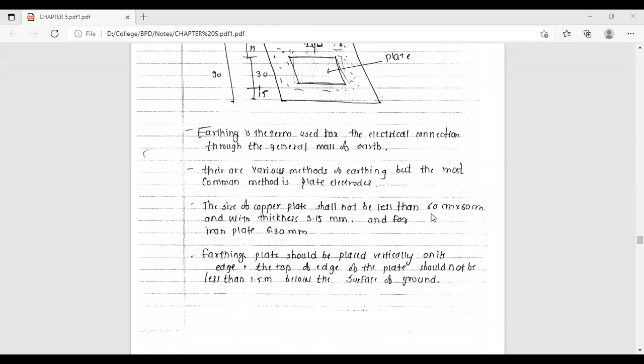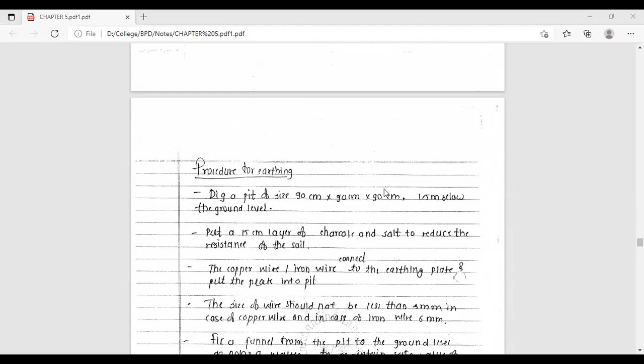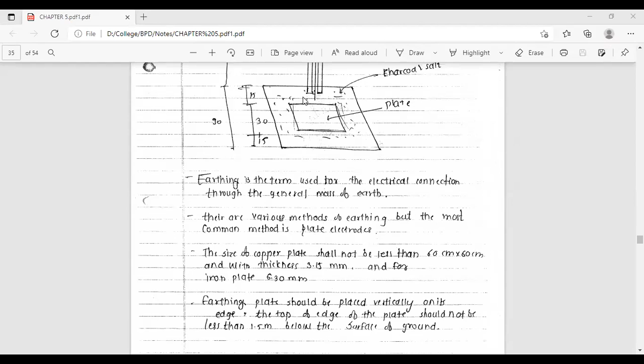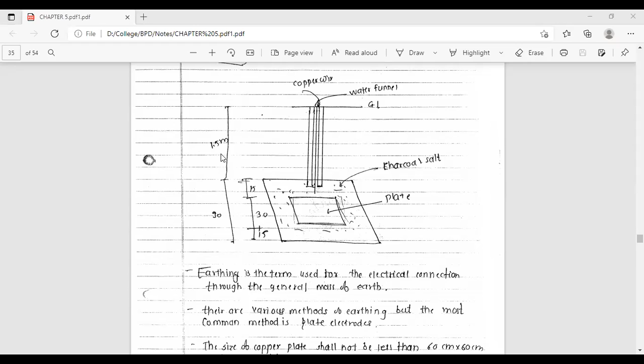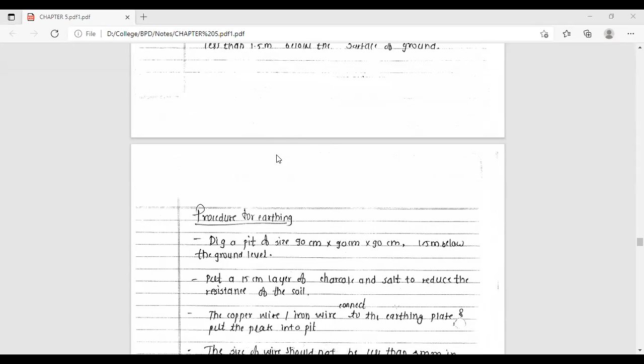Whatever the procedure for earthing, firstly we have to dig a pit whose size is 90 centimeter by 90 centimeter by 2.1 meter. Okay, because the height of that plate is 60 centimeter, and from the top edge of the plate, 1.5 meter distance should be there between the top edge of that plate and the ground surface. So 1.5 meter plus 0.6 meter, that is nothing but 2.1, or maybe you can increase it up to 2.3 meter also. Okay, so 90 centimeter by 90 centimeter by 2.3 meters, you have to dig and prepare a pit.